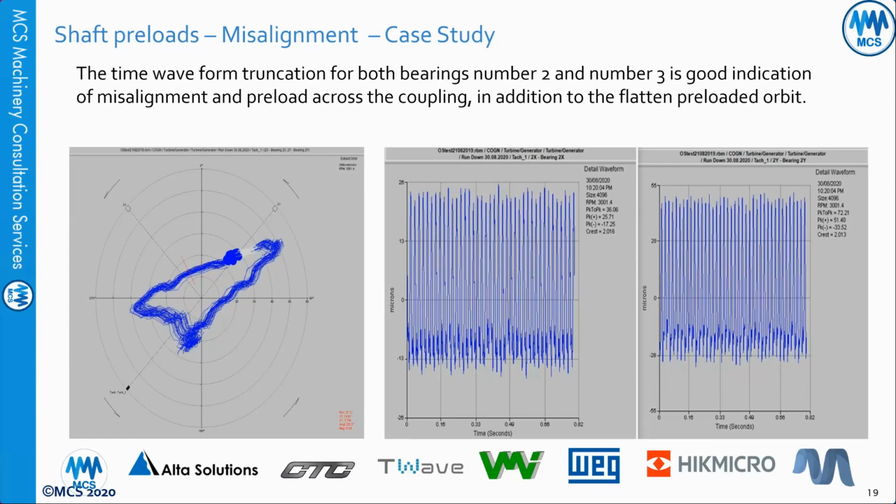There was a very famous case study from Mobius in category 3 for a condensate extraction pump, when they did balancing for it, and it was very good balancing as well. The shaft and all the load on the bearing was gone, and because of this, the bearing started to skid. When the bearing was skidding, because of the friction, the grease evaporated, went inside the vertical motor, and then it exploded. It was in one of the power stations here in Australia. And this is a similar thing.